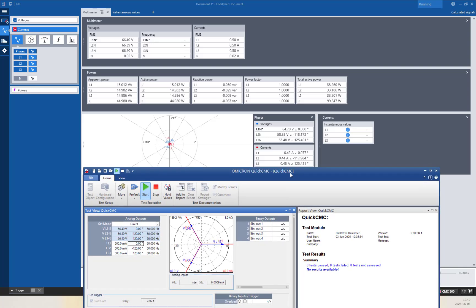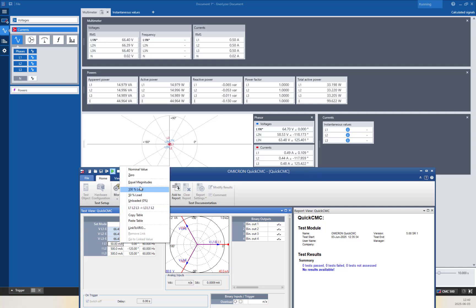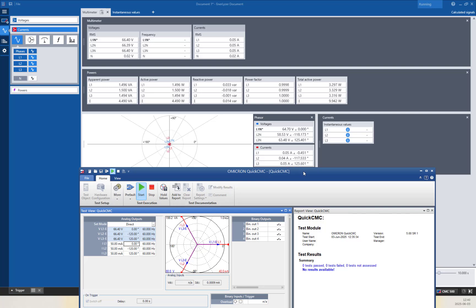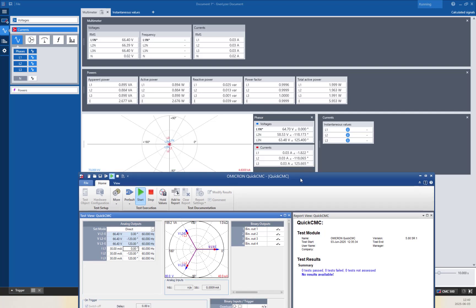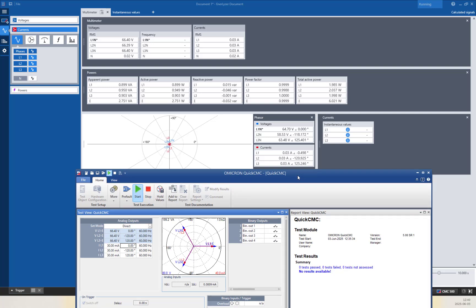Phase angle measurement for IL1, IL2, IL3 remains stable at 0°, approximately -118° and 125° — very close to the expected values. Decreasing to 50 mA and even 30 mA, the phase angle is still available with no weak signal error. This demonstrates the high accuracy of the CMC 500 with the new Analyzer module compared to the CMC 356 with the Analyzer Classic module, which would show a weak signal error below 2% of the nominal range. This is the main benefit and use case for the CMC 500 as the new benchmark in the testing field.